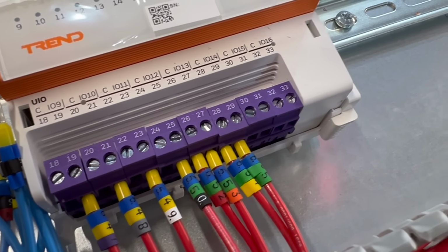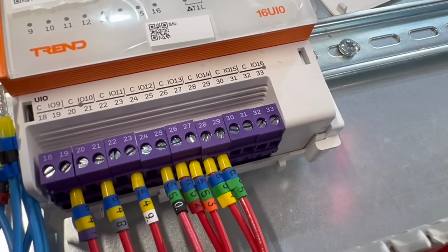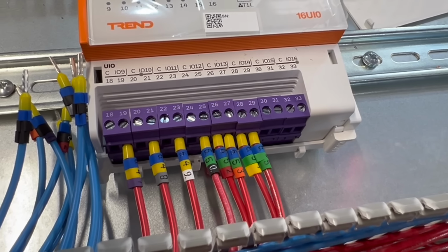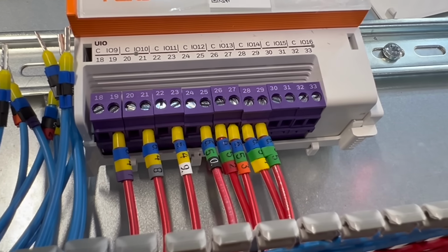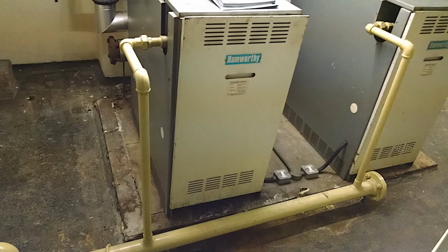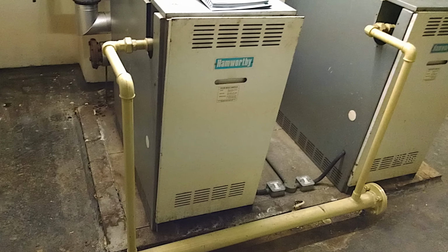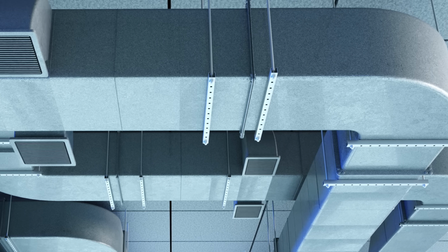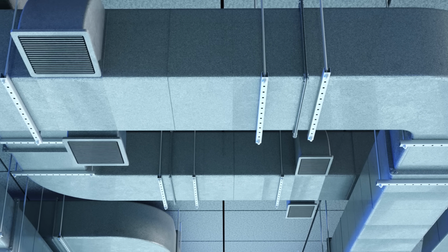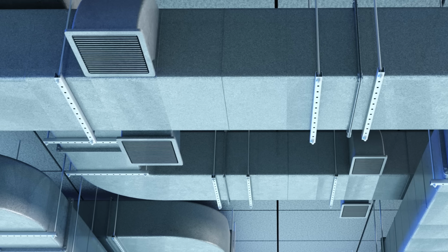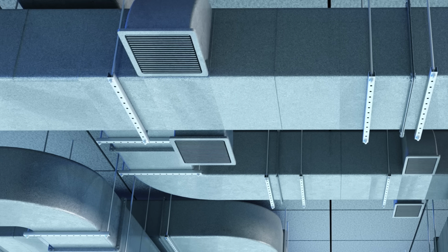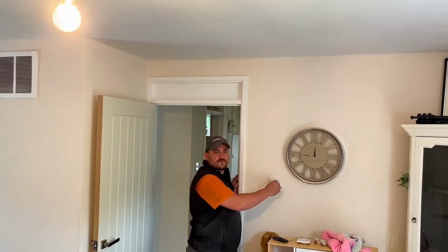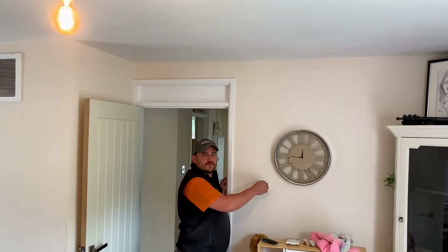Next up, we've got the outputs. These are the terminals where the DDC sends instructions back out into the world. Again, we've got digital and analog flavours. Digital outputs can turn things on or off, like firing a boiler or switching a fan to run. Analog outputs, meanwhile, can send variable signals, typically 0 to 10 volts, to modulate things like valves or dampers into specific positions. This allows fine control rather than just binary operation. Think of it like using a dimmer instead of a simple light switch.